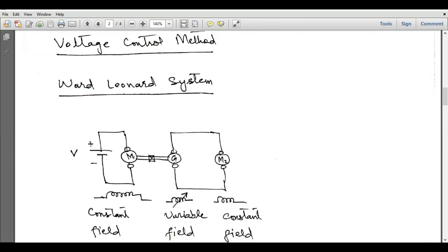The Ward Leonard system is used to control the speed of a motor by varying the applied voltage. If a variable DC supply is not available, a fixed DC supply is connected to a first motor M1, which is mechanically coupled to a generator. When M1 rotates, it drives the generator shaft. By changing the field current of this generator, we can change its output voltage, which is then used to control the speed of the second motor.